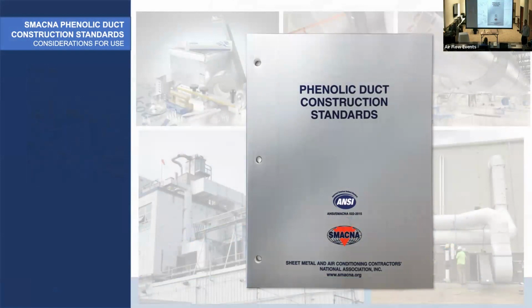So I'm going to talk a lot about phenolic duct. When we make duct out of phenolic, SMACNA, the Sheet Metal Contractors Association, has a whole standard book. When we build ductwork, we follow this book. There is another book for metal duct that looks exactly the same except it's metal duct instead of phenolic duct. This book gets updated and we follow it as closely as we can, so we maintain the warranty. When we build ductwork, it's got a 10-year warranty. We've had plenty of challenges over the years replacing phenolic ductwork that other contractors have made. This manufacturer that we work with upholds the 10-year warranty for real.